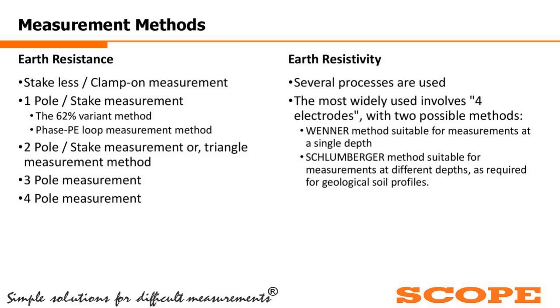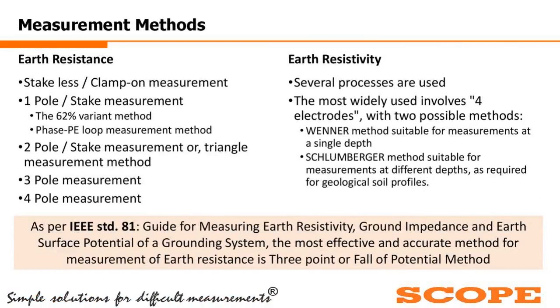So in the earth resistivity, Wenner's method is suitable for measurement at a single depth, and the Schlumberger method is suitable for measurement at different depths, as required for geological soil profiles. Now coming into the measurement methods in detail. However, as per IEEE Standard 81, the guide for measuring the earth resistivity, ground impedance and earth surface potential of a grounding system, the most effective and accurate method for measurement of earth resistance is the three-point or fall of potential method. So here lies the fall of potential, and how that method is explained, I will be coming into in the subsequent one.